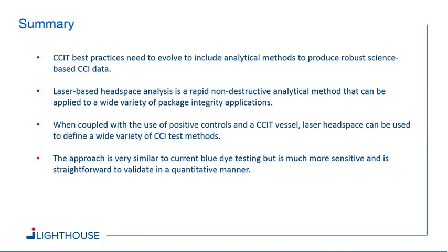And when you couple this technique with the use of positive controls and a CCIT vessel, laser headspace can be used to define a wide variety of CCI test methods which are really useful and add value through the whole product life cycle, whether you're talking about package development using empty containers, QC testing with real product containers, in manufacturing for either sampling or 100% inspection.